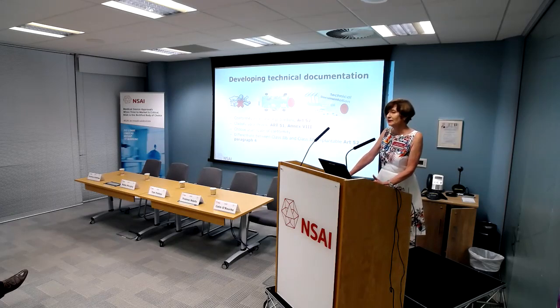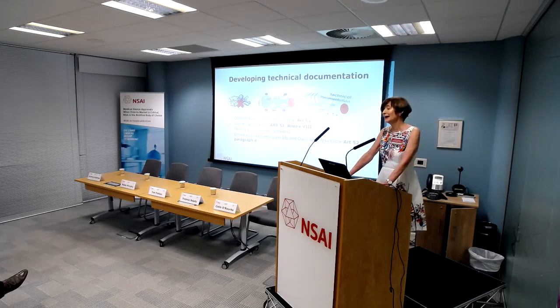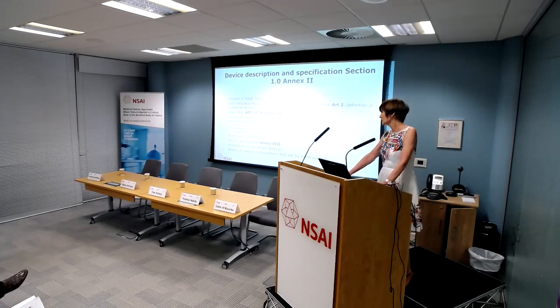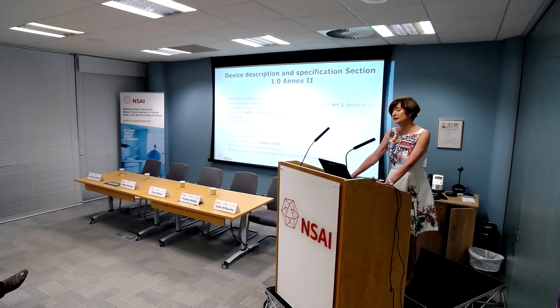The bulk of the data and the information is in Annex 9. Annex 10 is if you're doing type testing, and Annex 11 just refers you back to Annex 9. So Annex 9 is your go-to place. And then you need to differentiate between Class 2B and Class 2B implantable devices. They are treated very differently. A Class 2B implantable device is treated like a Class 3 device under the MDD. So we'll just briefly go through the different requirements, the different sections.